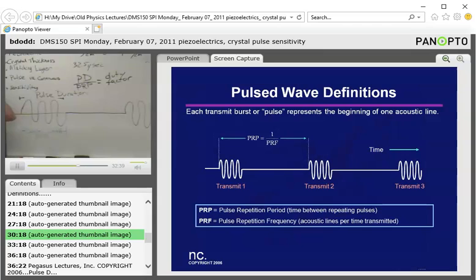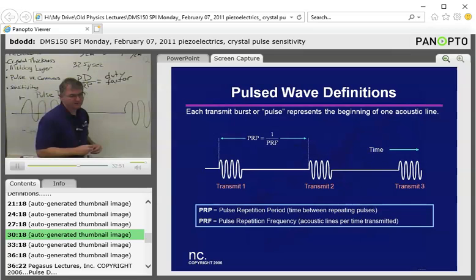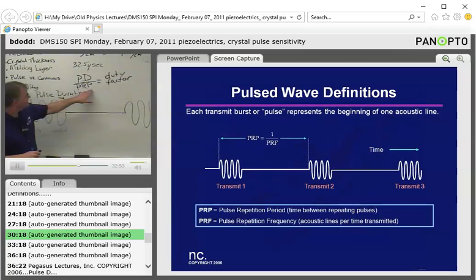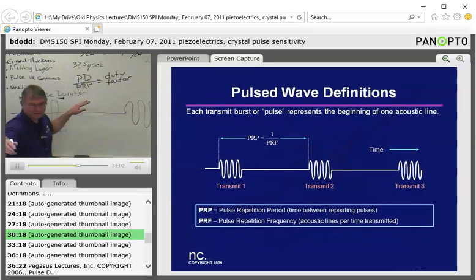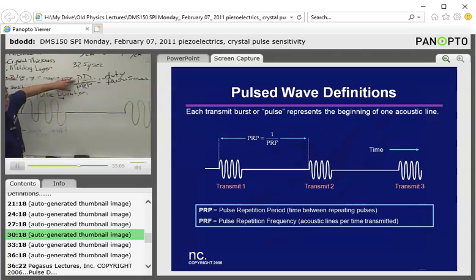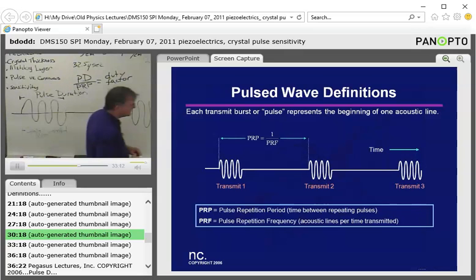And for those of you that have had small children, it's not the duty, duty. So it's the duty factor is what we call it. It's the pulse duration divided by the pulse repetition period. So if I increase the amount of listening time, if I increase my pulse repetition period, what happens to my duty factor? It goes down. Thank you. If I increase my pulse duration, what happens to my duty factor? Goes up. Very good. So you got that? Good.